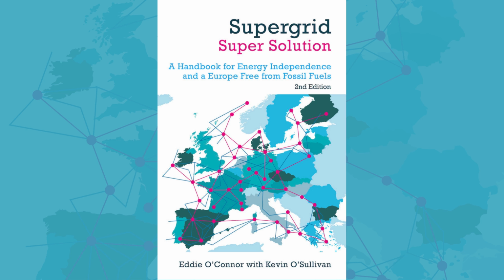Heat pumps represent a natural energy efficiency measure, as indeed the use of electricity to drive vehicles also does. To take a practical example for the individual householder, consider this: comparing a really efficient gas boiler with an efficient heat pump, taking energy prices as they might be in the medium term at €0.12 per kilowatt hour for residential gas and €0.35 per kilowatt hour for electricity. We'll consider turning the heating on for 5 hours a day for 180 days a year, which is quite a lot. Let's say 10 kilowatts of heating is required for the house, just for easy numbers, but it doesn't really matter, as we are comparing the same heat demand in the same house.